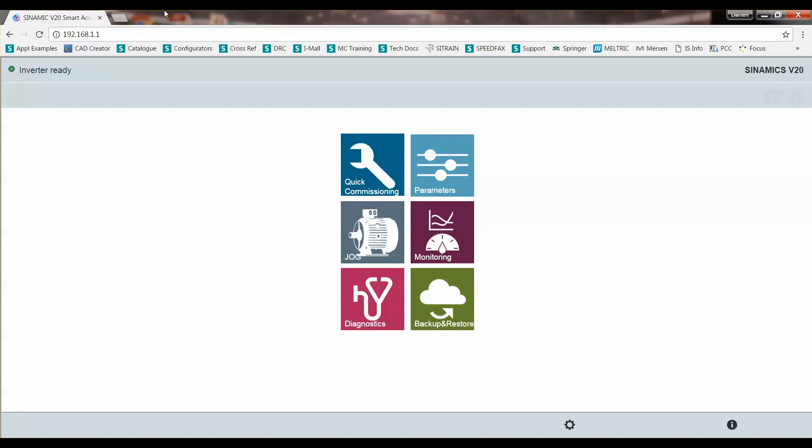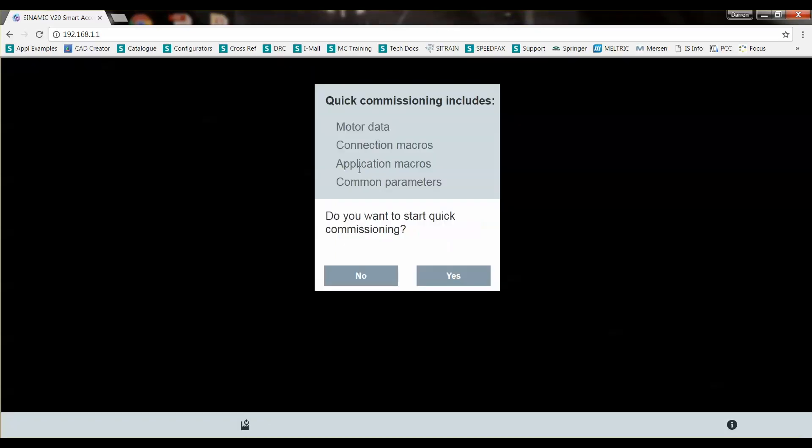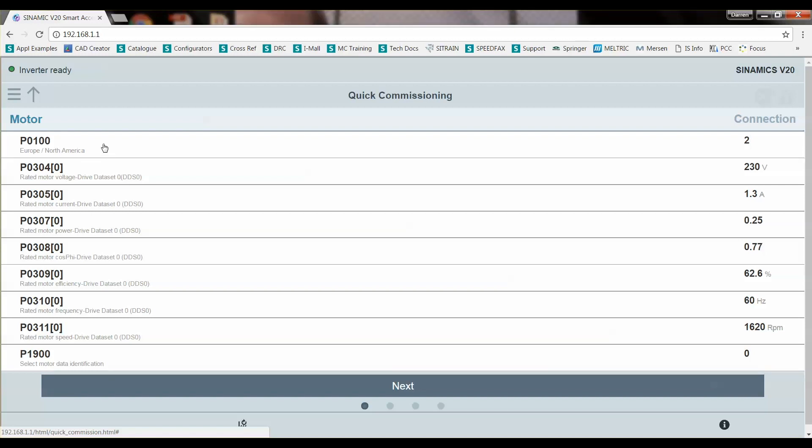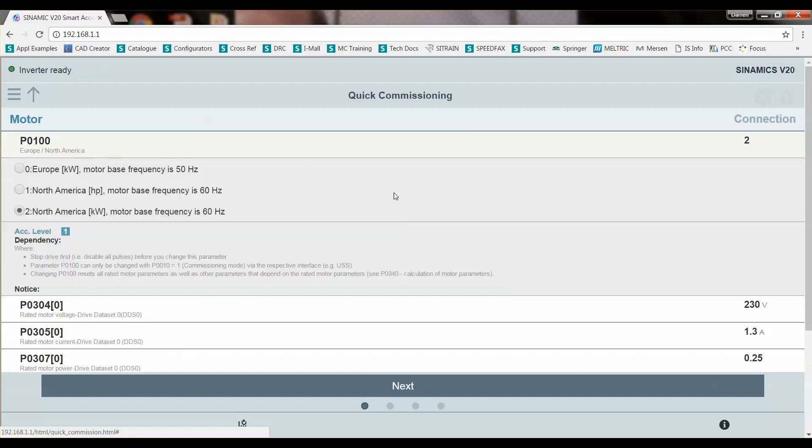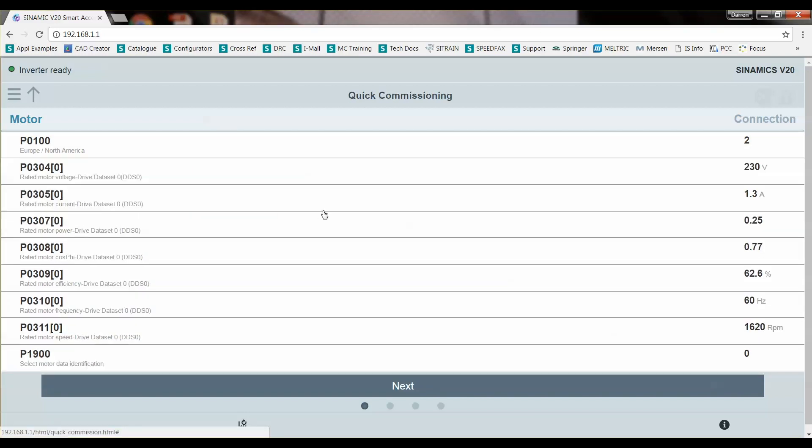You'll see that I've got a little indicator saying inverter ready, the green light. My menu is here and we're going to start with quick commissioning. So yes I want to commission the drive. We can look at what parameters are going to be modified during the quick commissioning. We're going to click on it to see what the choice is. It's North America kilowatt with 60 hertz rated. So that's what I want. Rated motor voltage 230 volts.